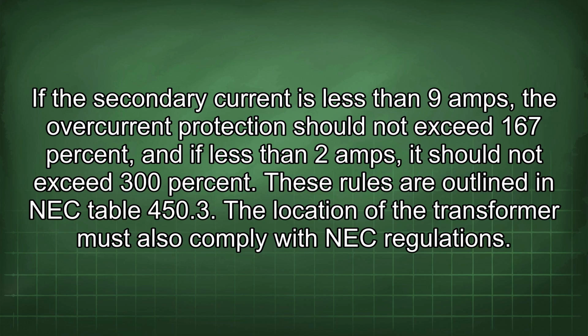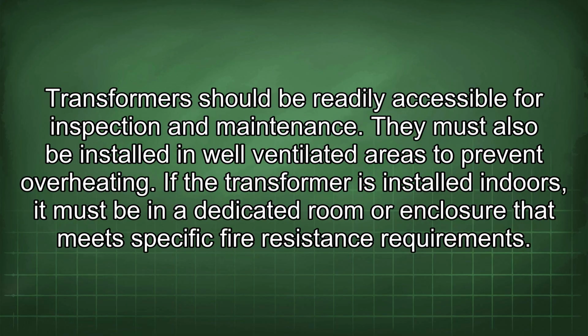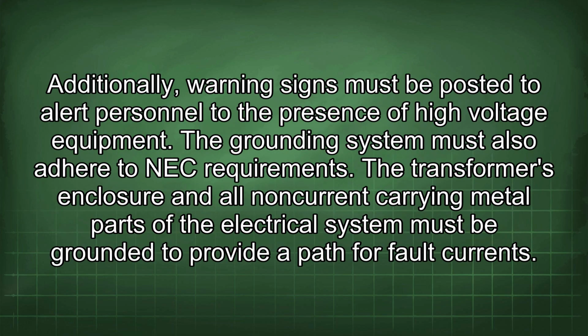The location of the transformer must also comply with NEC regulations. Transformers should be readily accessible for inspection and maintenance. They must also be installed in well-ventilated areas to prevent overheating. If the transformer is installed indoors, it must be in a dedicated room or enclosure that meets specific fire resistance requirements. Additionally, warning signs must be posted to alert personnel to the presence of high-voltage equipment.